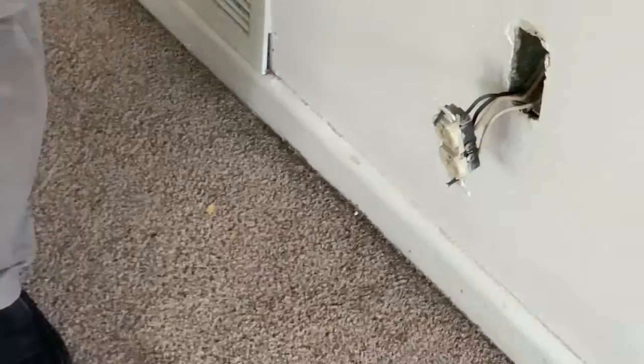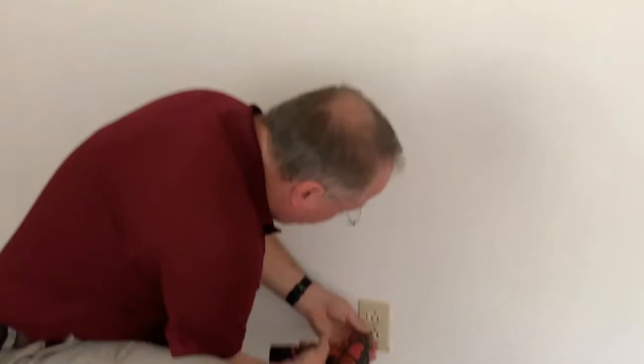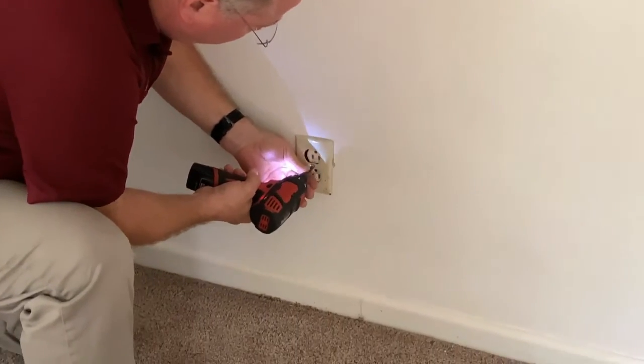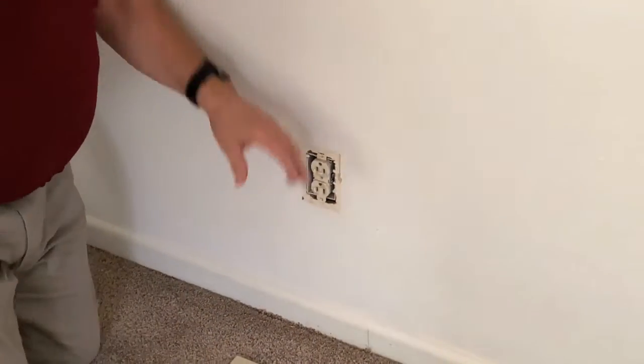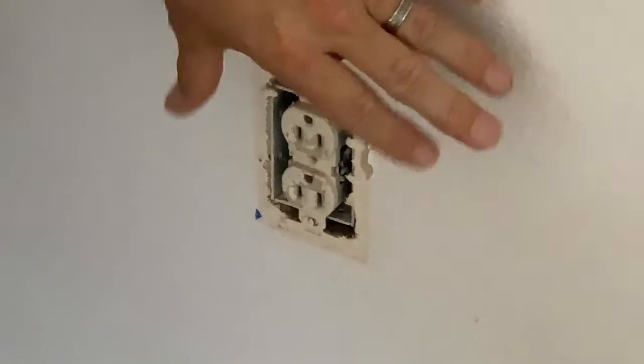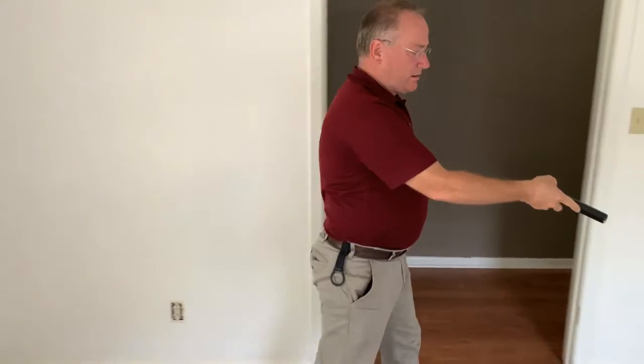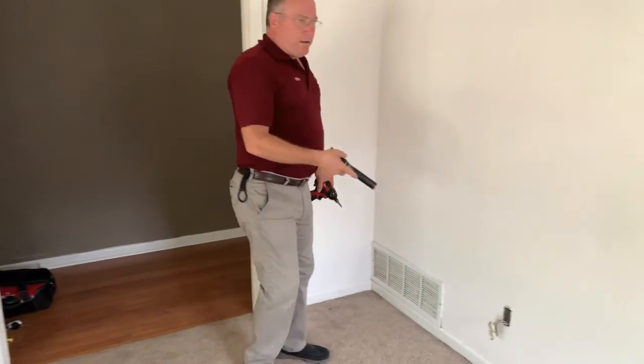Just to double check and also to show you how you can find the last outlet in the chain — I'm going to come over here and look in. I can see only one set of wires, so this will be the last outlet in this room. So it is almost certain that this here is the last outlet in the chain.